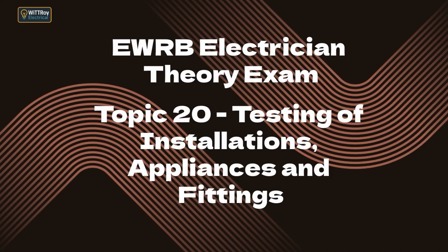Some fittings can be damaged by high-voltage insulation tests. These include LED fittings, electronic ballasts, electronic dimmers, surge protection devices, control circuits with sensitive electronics, smoke alarms, and some appliances left connected. These must be disconnected or isolated before insulation testing.